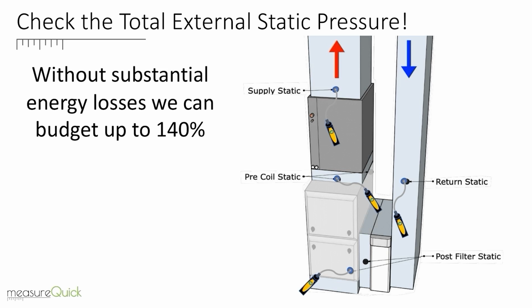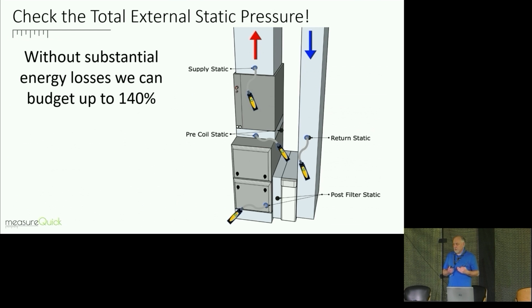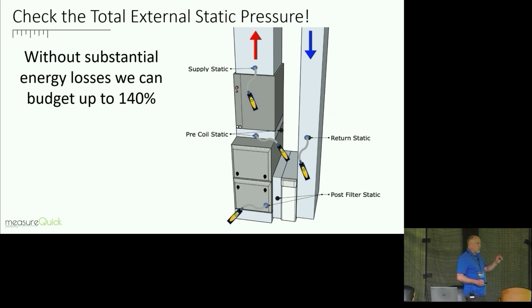You can actually go up to about 0.7 inches of static before you have significant energy losses, all right? I know it's rated at 1/2 inch. A lot of guys will say if it's above 1/2 inch, it fails, all right? But I'm telling you that you could fix it, and you get it down to 1/2 inch, so you get those 2/10, but you're not going to really see any substantial energy savings. Now, that said, you go above 0.7, and it's like a roller coaster going down, all right? Especially if you have a PSC blower motor. Anything on a PSC will really start to die.